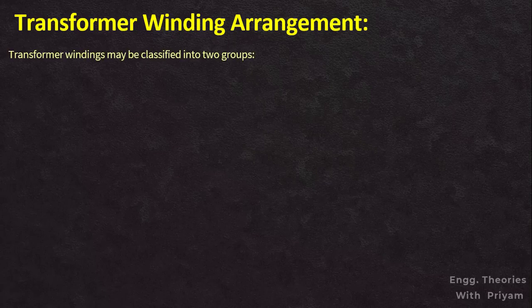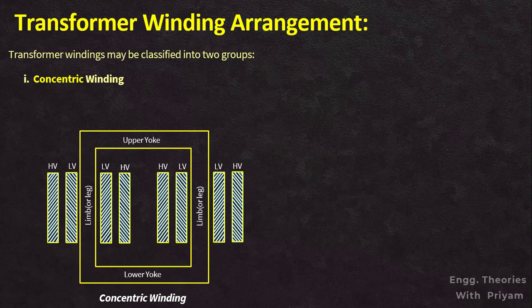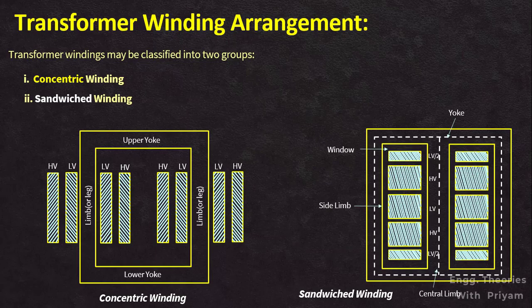In the previous lecture, we saw that high voltage windings or windings with a greater number of turns and the low voltage windings can be arranged in either concentric or sandwich arrangement. Concentric windings are used in core type transformers, while sandwich windings are almost exclusively used in shell type transformers. The positioning of HV and LV windings with respect to the core is important for insulation; low voltage windings are placed closer to the core, while high voltage windings are placed on the outside. The insulation spaces between the low voltage and high voltage coils also serve to facilitate cooling.